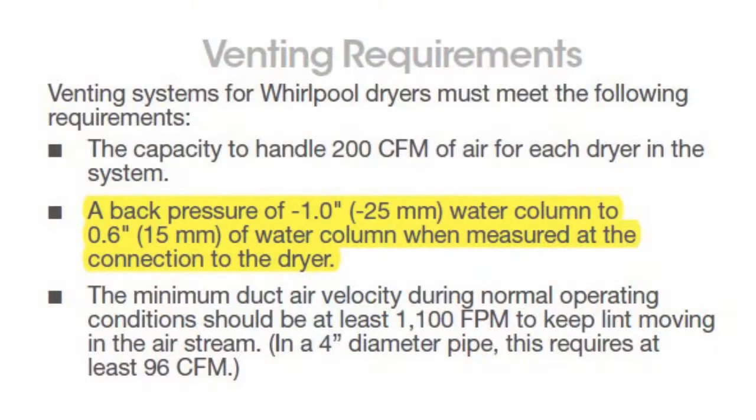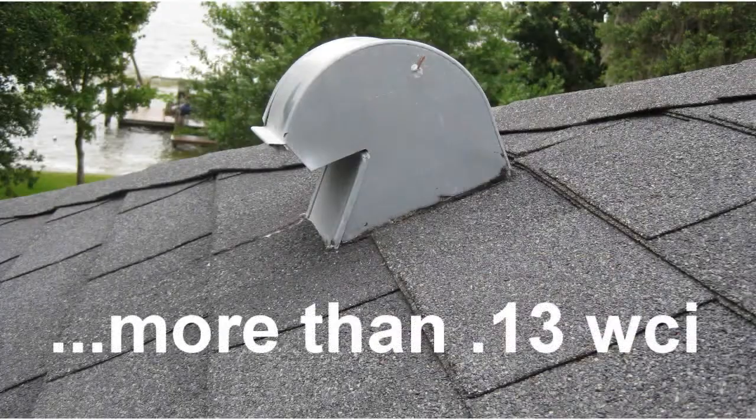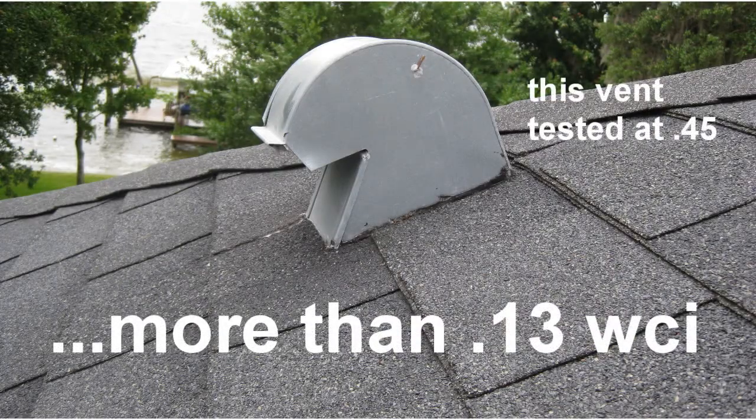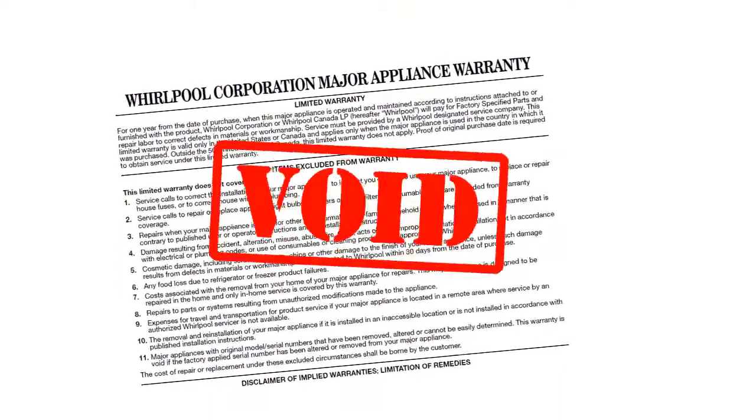What's interesting is that a popular appliance manufacturer requires dryer exhaust systems to not exceed 0.60 water column inch of pressure. In our typical scenario, a roof termination that provides more than 0.13 of pressure would violate the manufacturer's design limitations and possibly void the warranty.